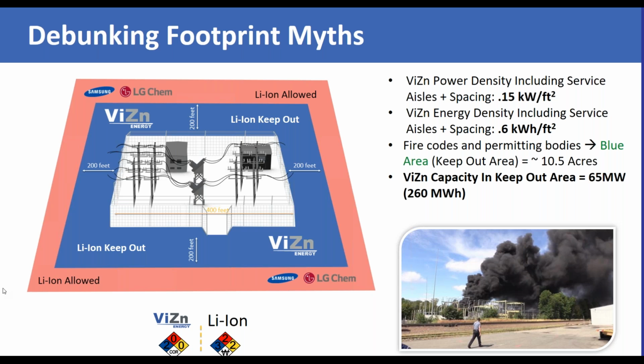On 3 separate utility scale projects recently, I've seen anywhere from a 200 to 250 foot minimum keep-out area - a minimum offset between the lithium-ion system and the high value grid infrastructure. Within that shaded blue area, that's about 10 acres. And ViZn can put 65 megawatts in 10 acres.